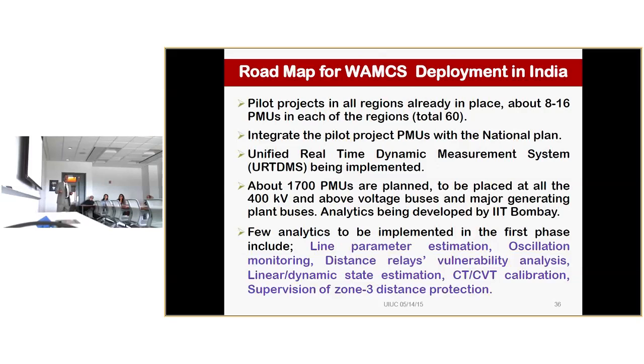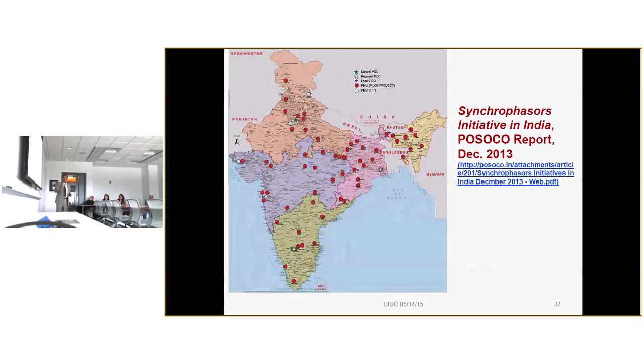So very soon we are going to have about 1700 PMUs covering all 400 kV buses and above voltages and all major generating stations. In the first phase, 1700 PMUs will come. A few analytics are being developed, and these will come in the first phase: line parameter estimation, oscillation monitoring, vulnerability analysis of distance relay, state estimation, CTPT calibration, CVT calibration, and supervision of zone 3 distance protection. These are already being developed, and now the equipment is arriving, and maybe within a year it will be deployed. And these are the 60 PMUs which were put across the country in 2013. There is a report which gives you the kind of experience they have with this particular tool.